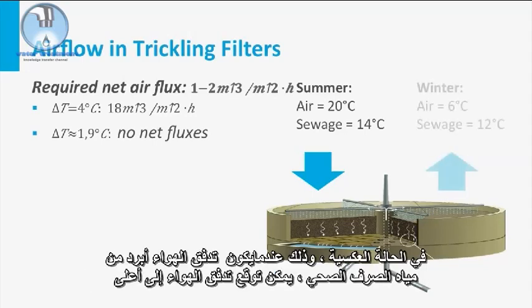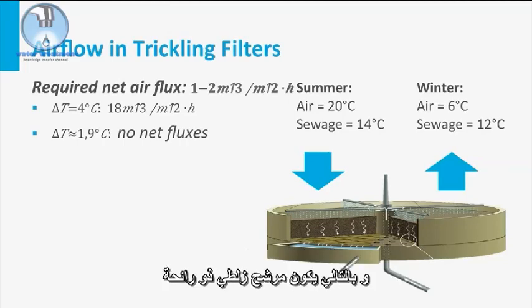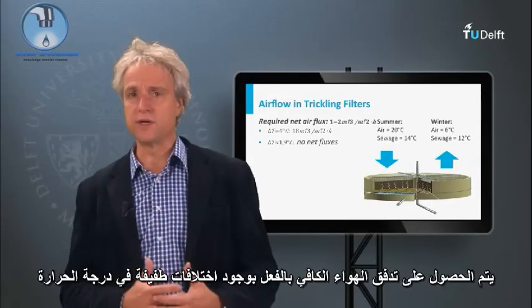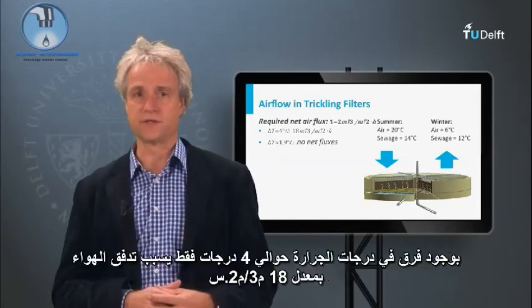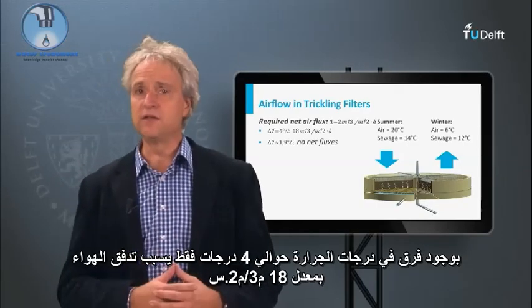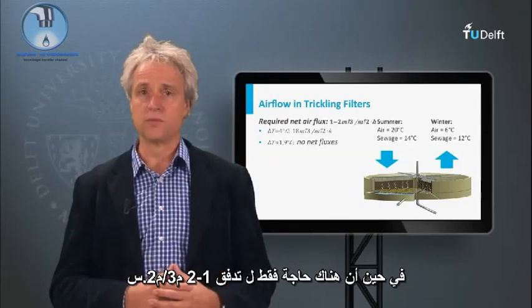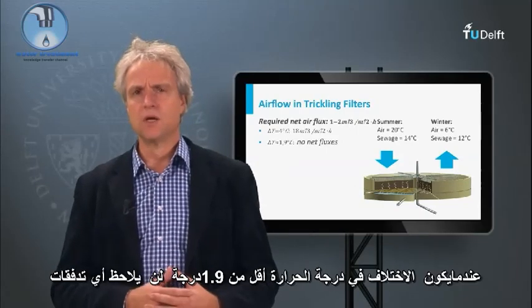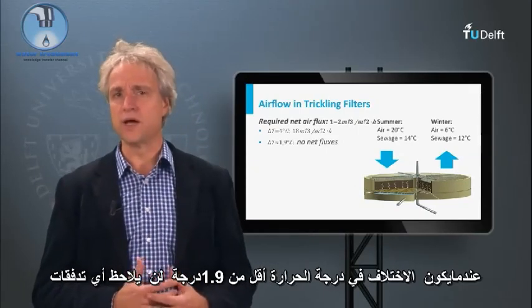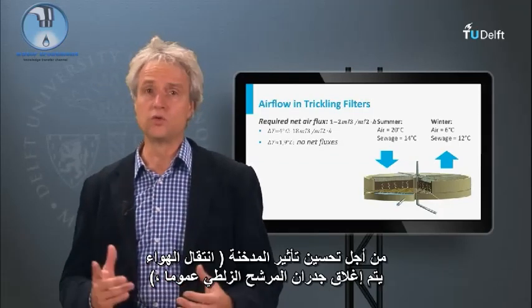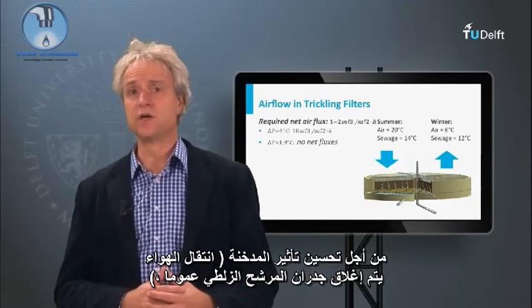In reverse situations, so when the airflow is colder than the sewage, an upward airflow can be expected and thus a more smelly trickling filter. Adequate airflow is already obtained with very little temperature differences. A difference of 4 degrees Celsius already causes an airflow of 18 cubic meter per square meter surface per hour, whereas only a flow of 1 to 2 cubic meter per square meter per hour is needed. When the temperature differences are less than 1.9 degrees Celsius, no net fluxes are observed. In order to enhance the chimney effect, the walls of a trickling filter are generally closed.